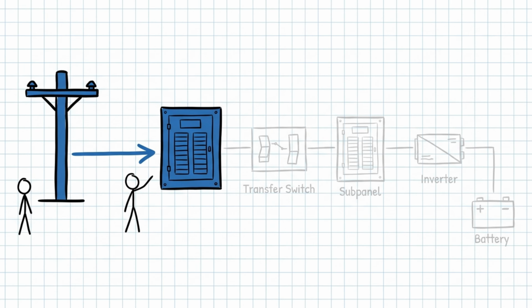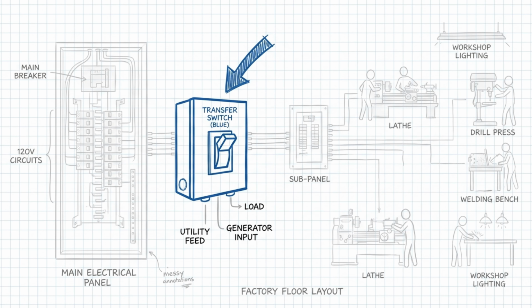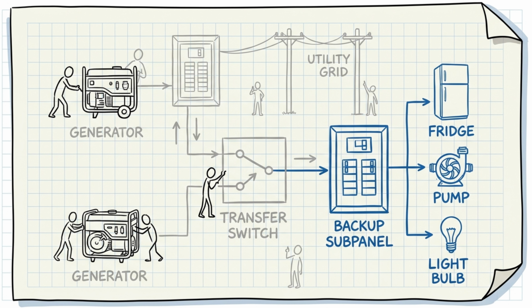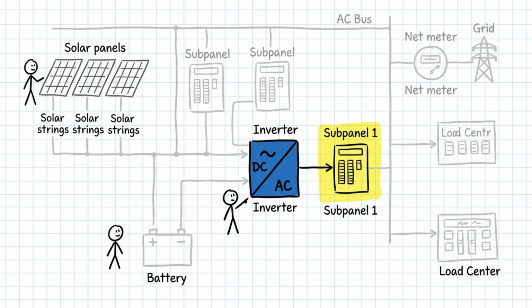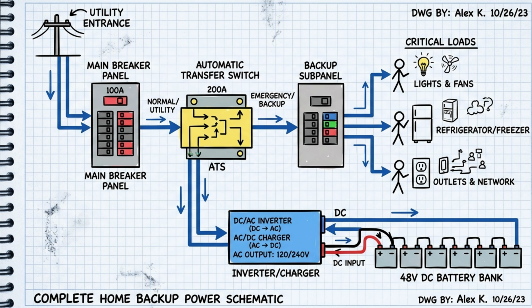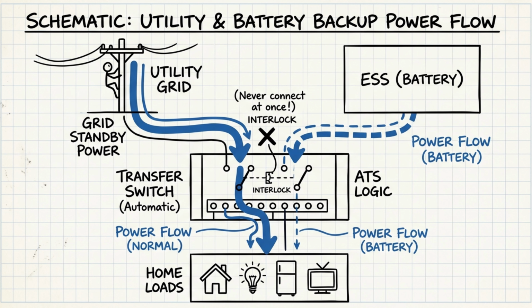Start at the utility service entrance, where grid power enters the house, then the main panel, which feeds every circuit under normal conditions. Between the main panel and your backup load sits the transfer switch, the one component whose entire job is deciding which source, utility or battery, touches the wires downstream, and making sure it's never both at once. Downstream of that switch is a backup subpanel, holding only the circuits you've chosen to protect: fridge, well pump, a few lights. Feeding that subpanel is the inverter, converting your battery's direct current, or DC, into the alternating current, or AC, your appliances expect. Behind the inverter sits the battery bank, the energy reservoir the whole system draws down during an outage. One-sentence version: power normally flows straight through from the grid, but the moment utility power drops, the transfer switch disconnects that path completely before it reconnects the backup subpanel to the battery's inverter. One source, one direction, one connection at a time.